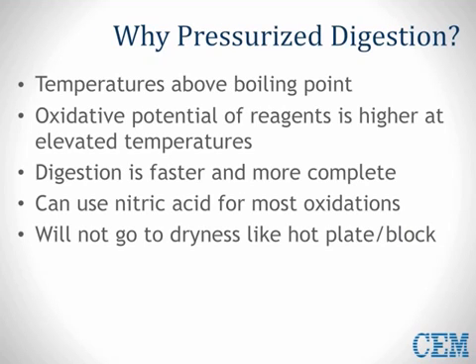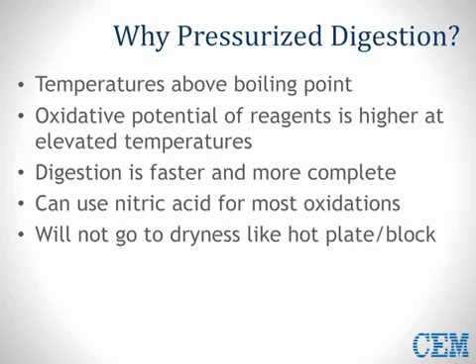For this reason, we must digest the sample using acids to destroy the matrix, leaving the analytes in solution. Pressurized digestion allows one to heat acids above the boiling point, which increases the oxidation potential for certain acids like nitric, as well as increasing the solubility of the solution — think of how hot water will dissolve more than cold water. The digestion process also goes much faster and provides a more complete digestion as compared to hot blocks.